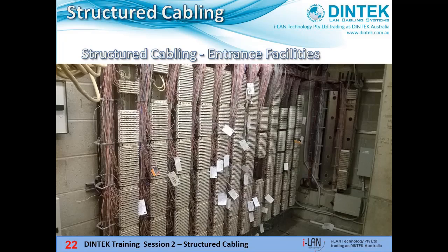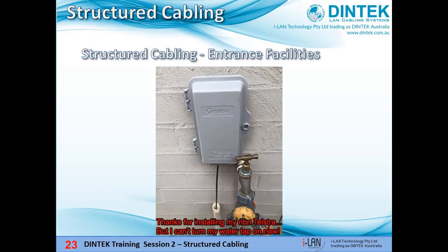This is what the entrance facility looks like in a large commercial building. You can see all of the carrier's red and white jumper wires connecting the building's telephone system into the carrier's network. Here we'd also find optic fibre links to other buildings in a campus situation. And this is what the home version of entrance facilities usually looks like. Note that gap between the conduit and the bottom of the enclosure — it's done quite deliberately to prevent any gases or water in the underground network from entering the customer premises. In the case of water it's particularly important when the building is below street level.